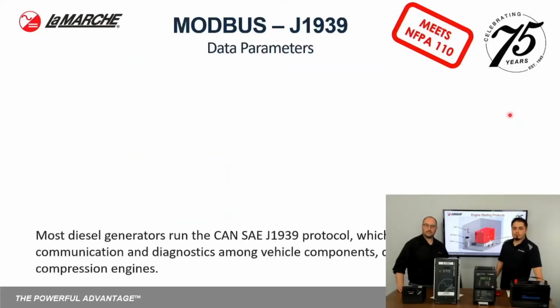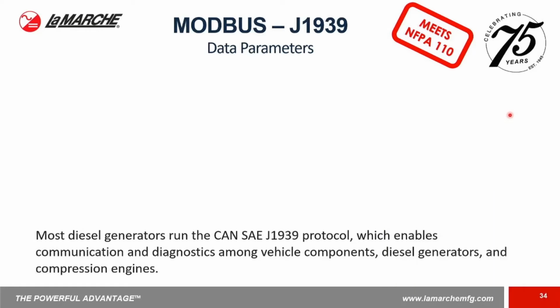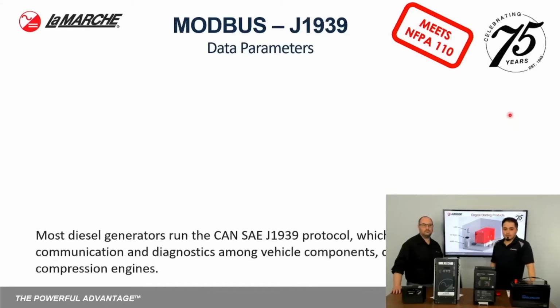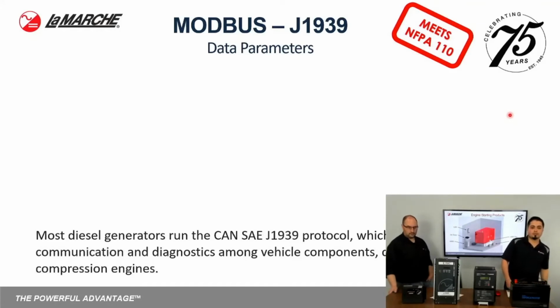Now, another very important feature that we have as a standard on the USE is going to be the Modbus J1939. This is now, as I mentioned, a standard feature. It's very important to us to keep up with the industry, as we are seeing most diesel generators now run on this protocol, which is CAN SAE J1939. This is much easier as far as diagnostics and communication back and forth with your charger, your control panel, your generator panel, and other components on site which run off the same protocol.